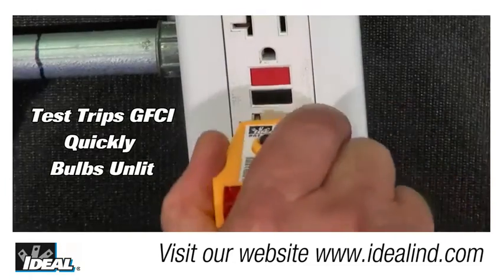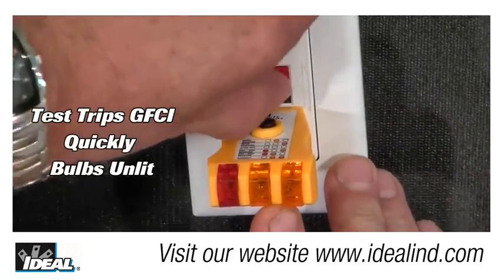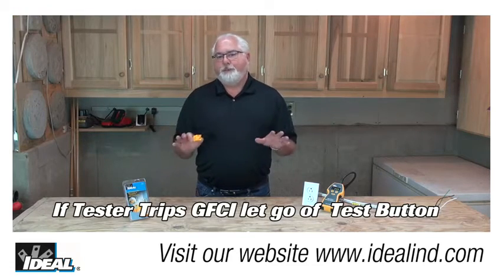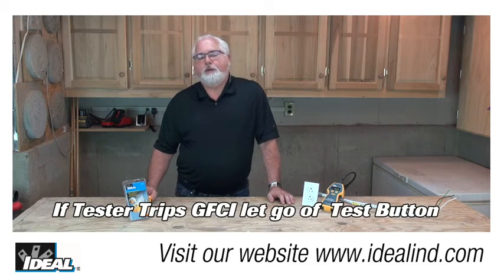And you're going to simply plug the tester into the GFCI, and with both bright bulbs lit, simply push the test button on the top of the tester for a minimum of 6 seconds. Now, usually the GFCI under test is going to trip immediately, and both bulbs on the tester are going to go out, but older GFCIs may take actually a little longer.